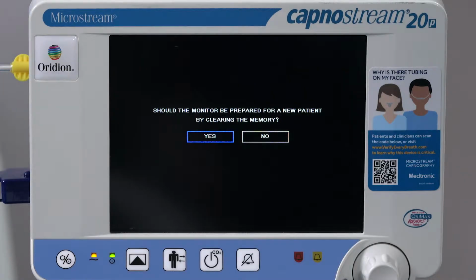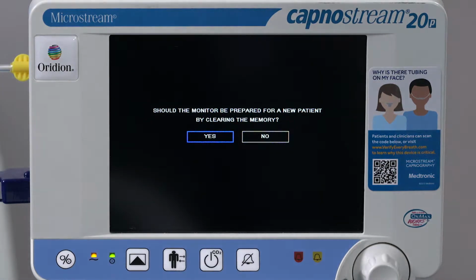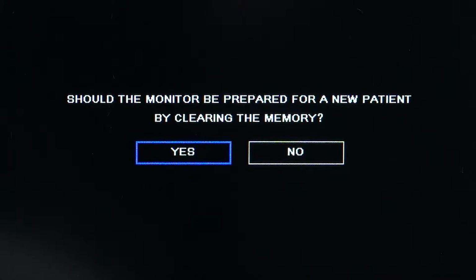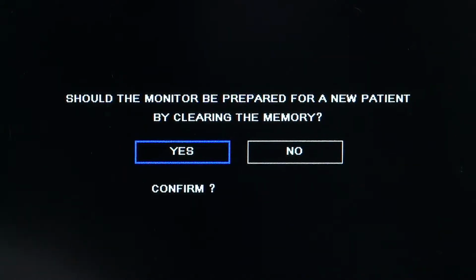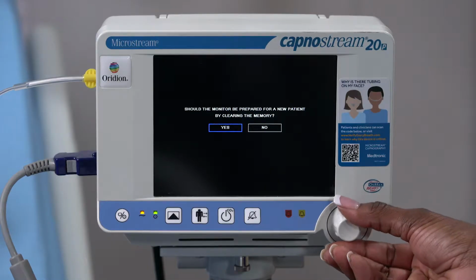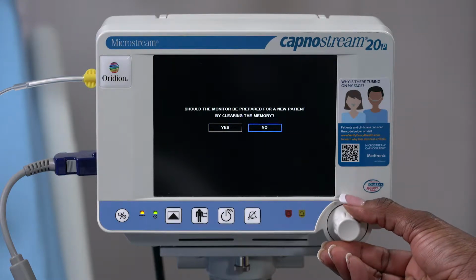Once powered up, the monitor will always ask a question. Should the monitor be prepared for a new patient by clearing the memory? If it's the same patient, then hit No. This will save the patient history. If it's a new patient, select Yes, which will erase any memory so you can start over. Selecting Yes erases the memory up to 72 hours worth and resets the patient alarm limits per the institutional default set by your facility. Selecting No keeps up to the last 72 hours of memory for that particular patient.